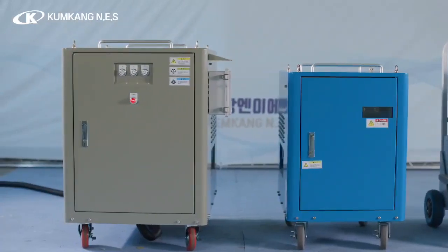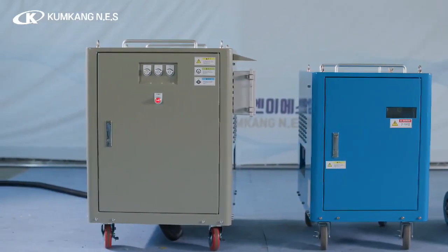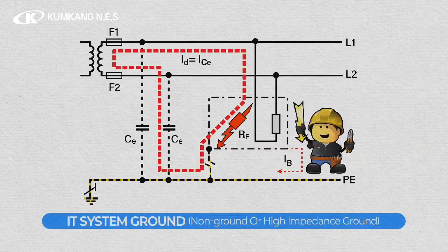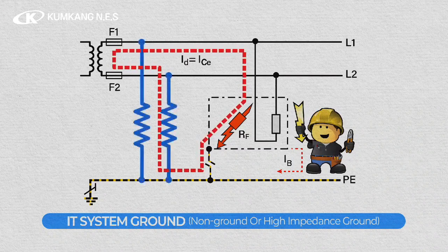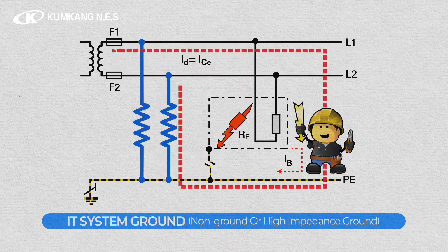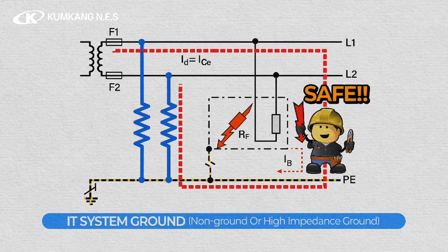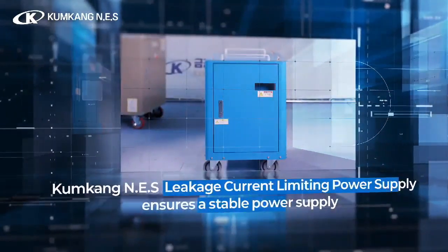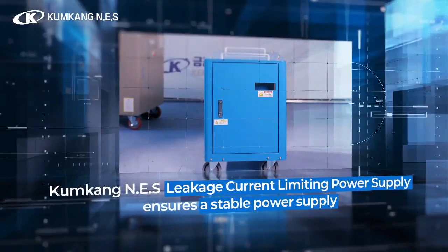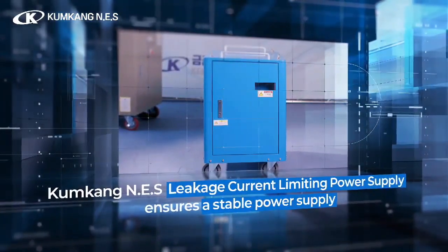In contrast, Kumkang N.E.S leakage current limiting power supply grounds the power system with high impedance, converting the traditional TN or TT system to an IT system. The leakage current is limited by the high impedance of the fault loop and the human body's resistance. The power supply minimizes the risk to people and equipment that can arise from leakage current. Kumkang N.E.S leakage current limiting power supply ensures a stable power supply.